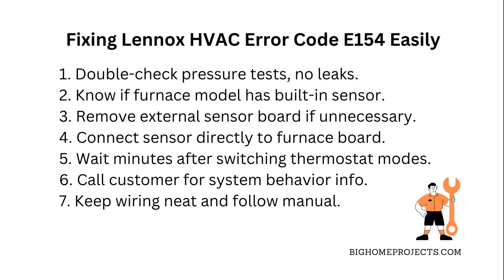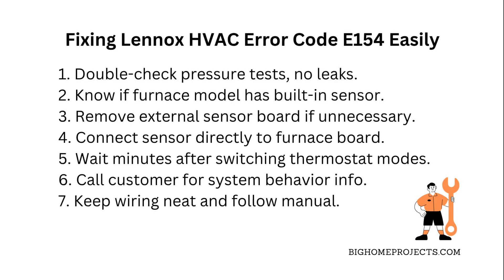For furnaces with a K in the model number, you don't need that external refrigerant detection sensor board, because the sensor terminals are built right into the furnace board itself.